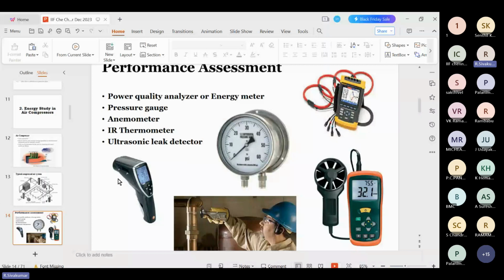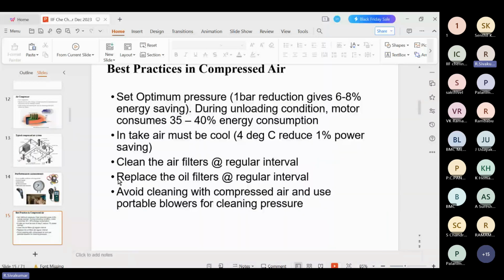But with this ultrasonic leak detector, even while the foundry is running, we can identify the air leakages, and some advanced instruments are available. How much CFM is leaking at a particular point can also be derived from the ultrasonic leak detector. Some of the best practices followed in the air compressor: set the optimum pressure. A 1 bar reduction will give 6 to 8% energy saving.